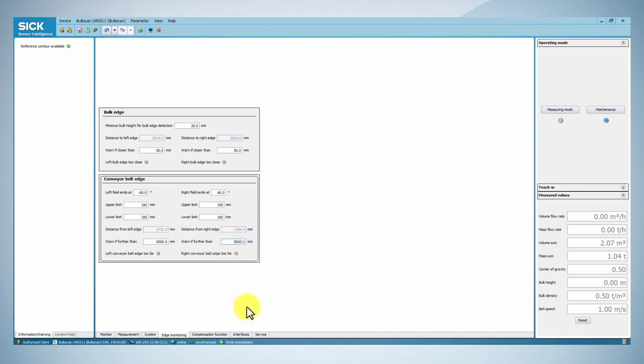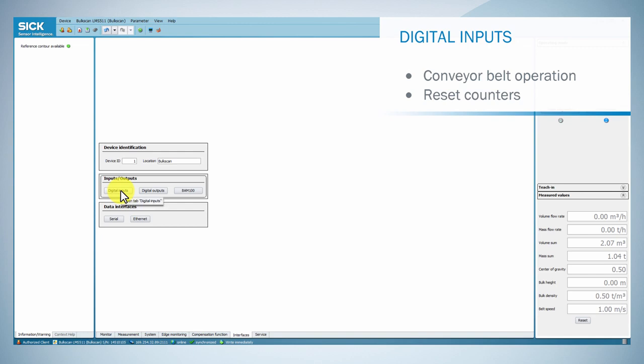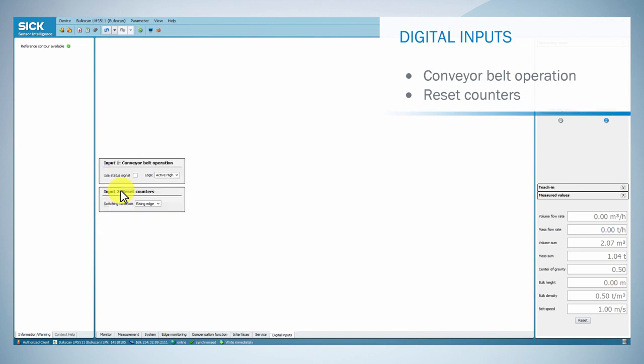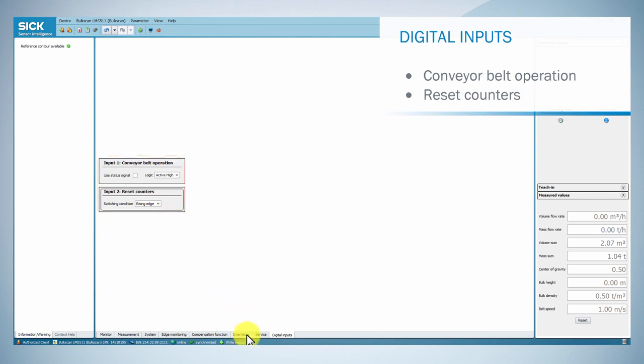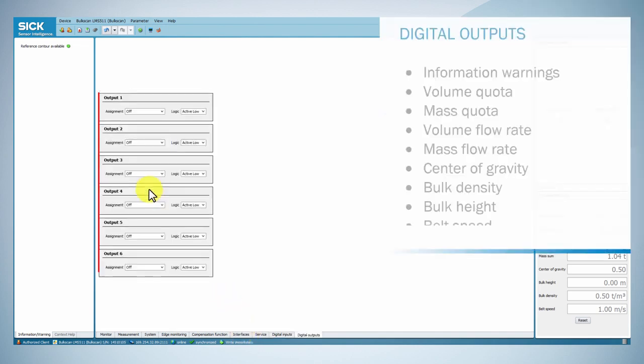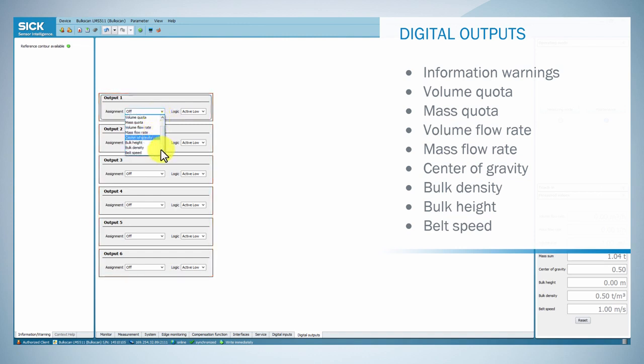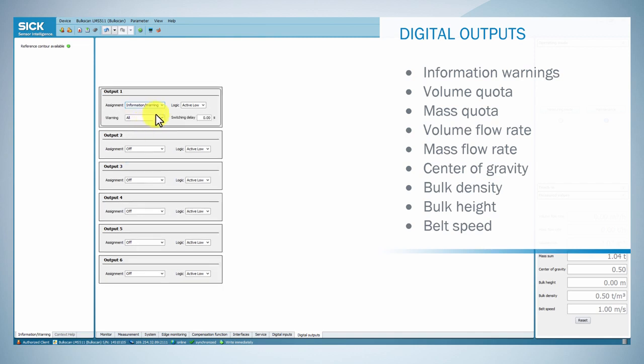The Bulkscan LMS511 has two digital inputs which are used to signal the belt operation and reset the volume sum and mass sum. It also has six digital outputs in which the sensor can signal that certain totals have been reached, limits have been exceeded or dropped below, or the occurrence of information warnings.